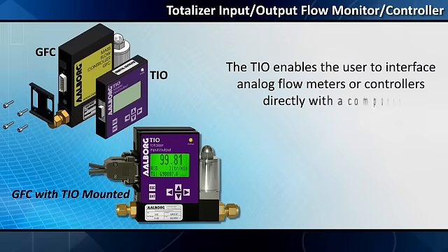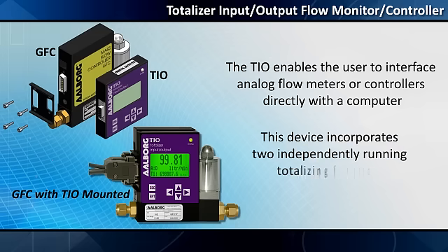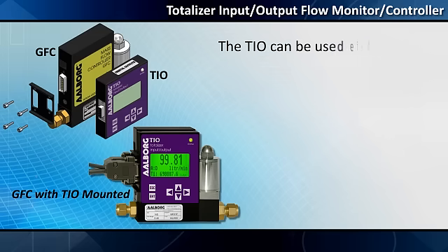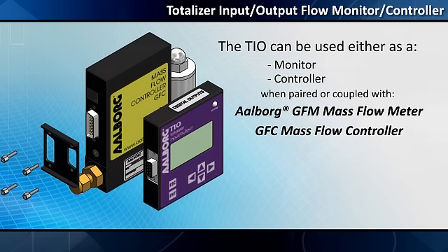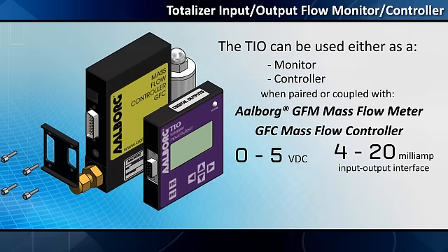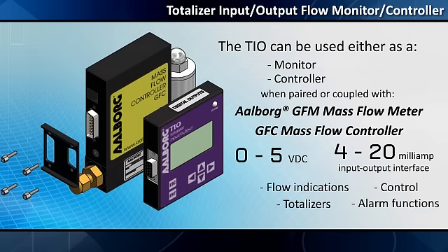The TIO enables a user to interface analog flow meters or controllers directly with a computer. In addition, this device incorporates two independently running totalizing functions. The TIO can be used either as a monitor or a controller when paired with an Aalborg GFM mass flow meter or GFC mass flow controller, and it is equally as versatile with any third-party device equipped with a 0 to 5 VDC and/or a 4 to 20 milliamp input-output interface where flow indications, control, and totalizer or alarm functions are required.